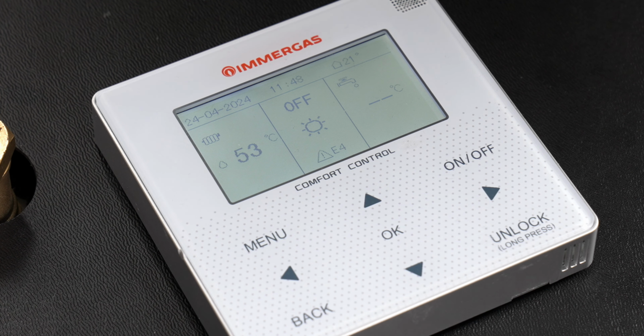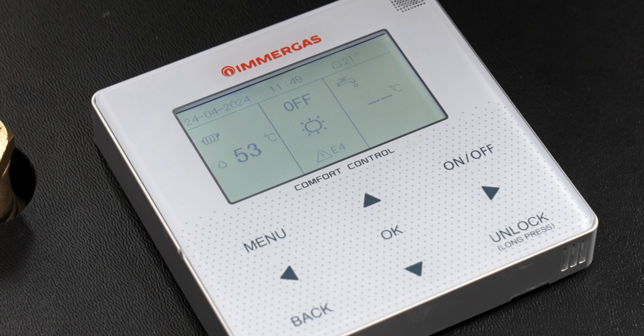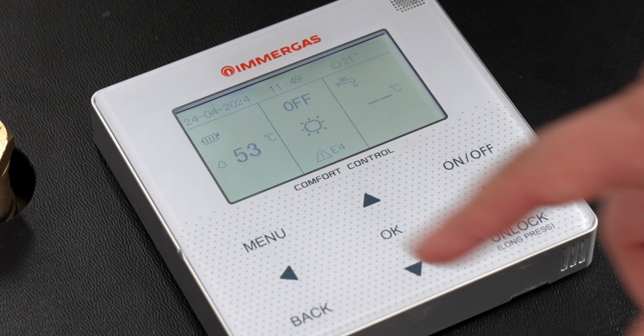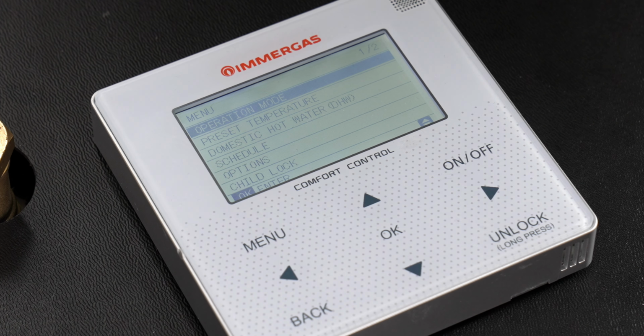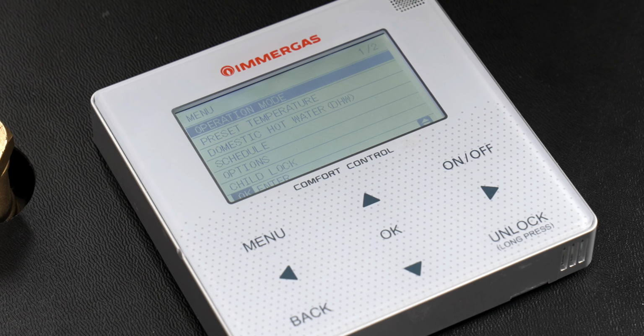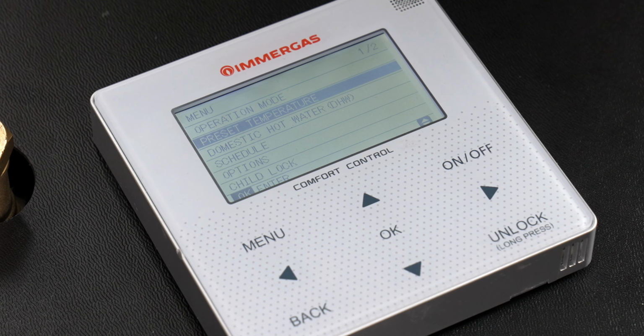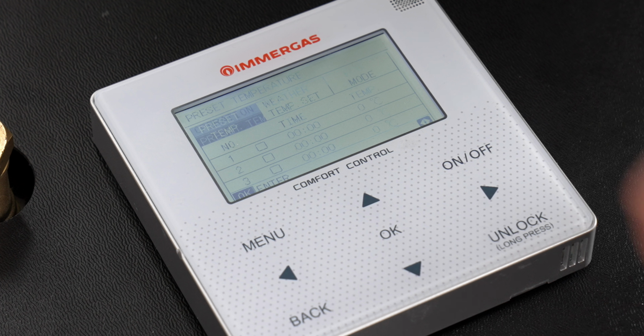The next thing you will see is on the left hand side, you will see a symbol for heating. In the middle it will say off, and on the right hand screen you'll see a hot water tap. I want to individually talk you through how to set all of these up on the controller. So we're going to press menu. The first thing we're going to do is make sure the weather compensation is on. So it's in preset temperature. So you come down one and then you press OK.